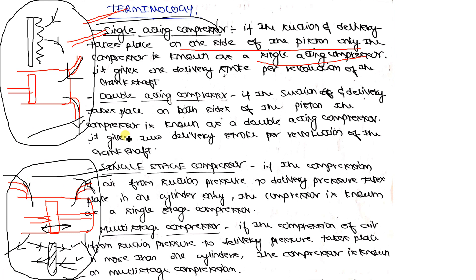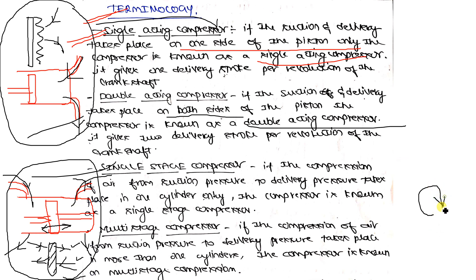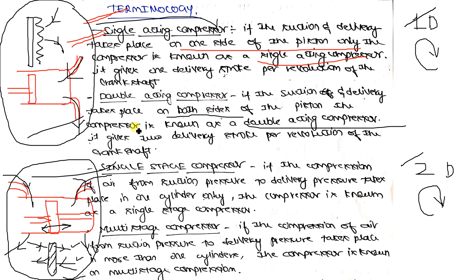In a double acting compressor, suction and delivery takes place on both sides of the piston, giving two delivery strokes per revolution of the crankshaft. In a single acting arrangement, there is one delivery stroke for every revolution of the crankshaft, whereas in a double acting compressor there are two delivery strokes for every revolution.